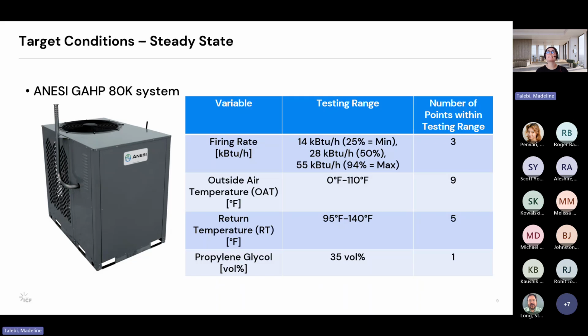And then for the steady state testing, this is a high-level overview. Looking at the firing rate, we're breaking it up into 3 different points. That being 25%, which we're calling the minimum firing rate that you would ostensibly see the ANESI unit at, so that's about 14 kBtu per hour. Right at the midway point, 50% of its firing rate capacity, so 28, and then 94, so not quite 100, but 94 is the max that the ANESI unit is able to fire at, given the modulating controls that are integrated into the system.